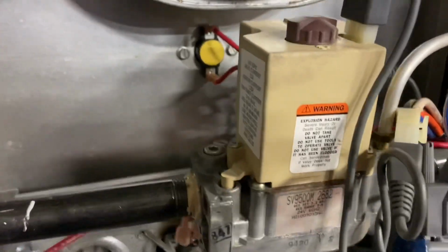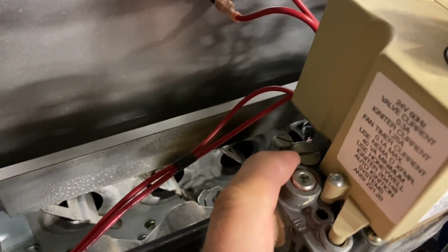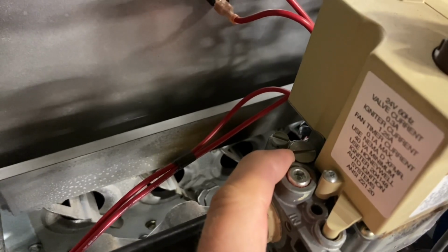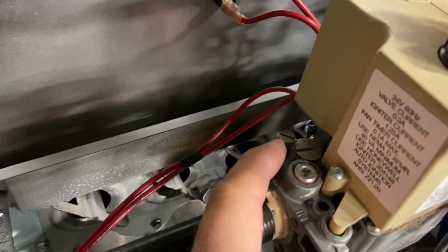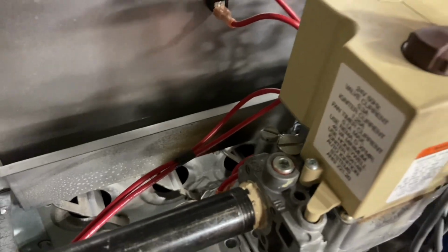Also, if we notice on the back side of this, there's two different screws right there. We take that cap off, and behind that's the adjustment for the gas pressure for the manifold, and this is the adjustment for the gas pressure for the pilot, for the intermittent pilot.